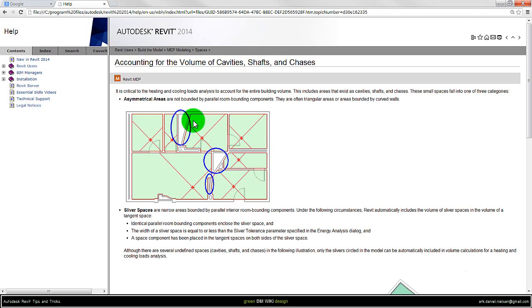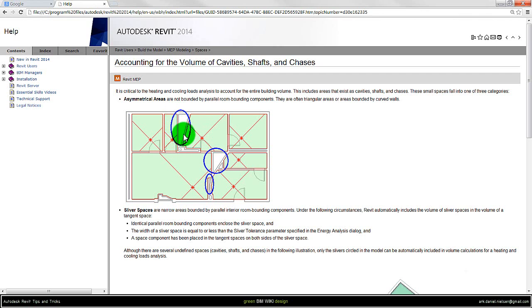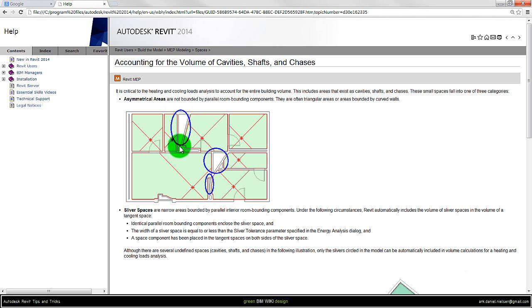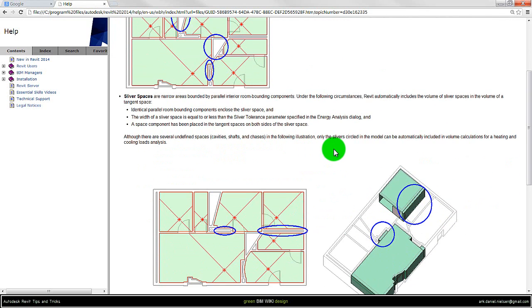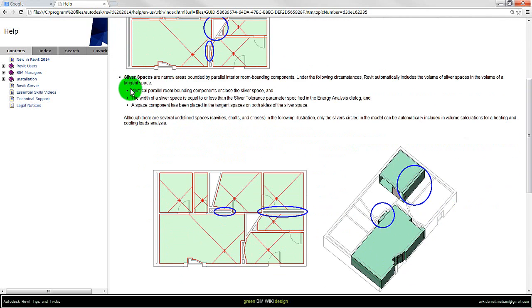So we have a model or zone model for the whole entire building. And if we didn't edit the sliver tolerance, then this would be considered as external surfaces and will have a huge heat loss. But actually it is not an exterior surface. So that is why it is important to look into this sliver spaces.